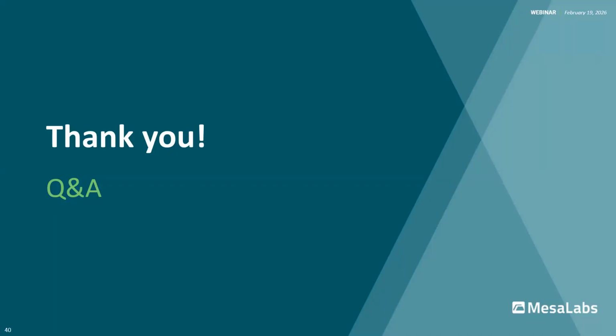Thank you. The next question I have is, does Mesa Lab flow meter automatically correct the flow rate to standardized temp and pressure? It depends upon the model. And Ron probably knows the fine distinctions better than I do. Some are pure volumetric, some display temperature and pressure, and some will actually calculate a standardized flow. Ron, do you have anything to add to that? Yeah, so the Defender 530 Plus series calculates that for you, so it removes any potential for error. As Lawrence mentioned, there are two other models, the 510s, which does just the volumetric. The 520 captures both temperature and pressure. But we always recommend the 530 Pluses that do the calculations for you.